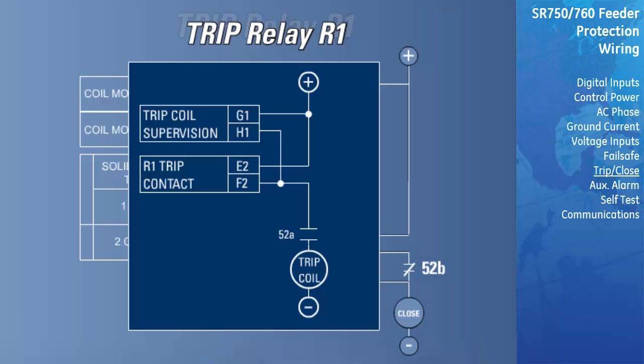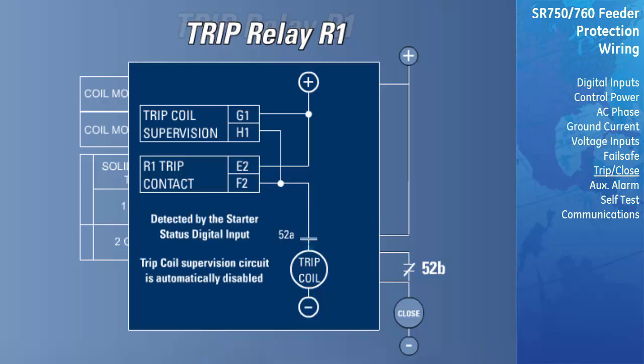Circuit breakers equipped with standard control circuits have a breaker auxiliary contact permitting the trip coil to be energized only when the breaker is closed. When these contacts are detected to open by the 52A or 52B inputs of the relay, the trip coil supervision circuit is automatically disabled. This logic ensures that the trip circuit is monitored only when the breaker is closed.